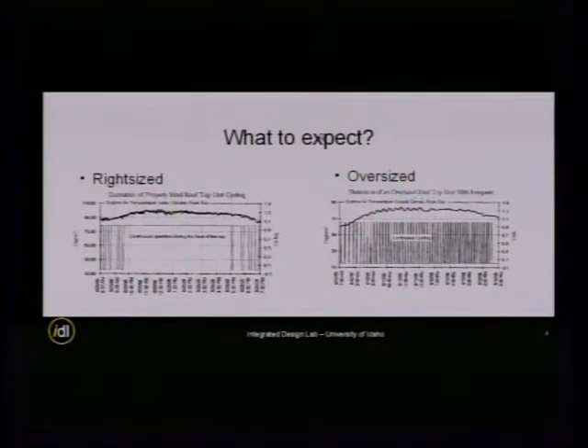So what we want to study is, we want to look at how many units out there are right sized, and we want to measure. And what we expect is to have, this is the outside air temperature right here, and this is the compressor operation. For the right size unit, during the peak condition, it will operate continuously, never off. This is what we expect, and this is what we call right-sized.